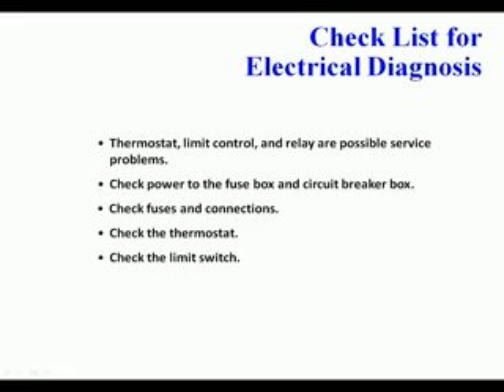Things you want to check are the thermostat, limits, control, and relay. Check the power at the fuse box and circuit breaker box. Check fuses and connections. Check the thermostat. Check limit switches. Check relay coils. Check relay points. And check electric heating coil circuits.